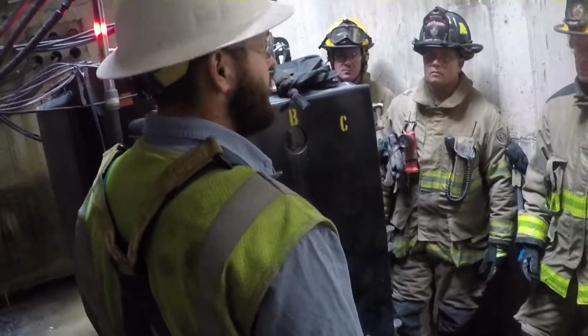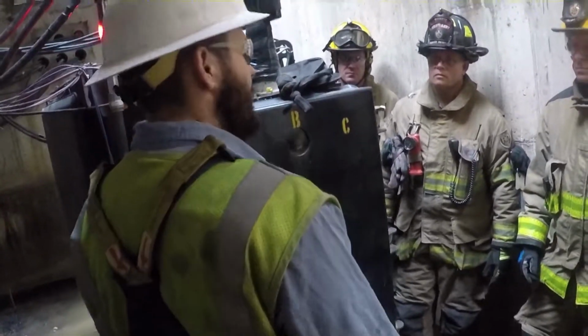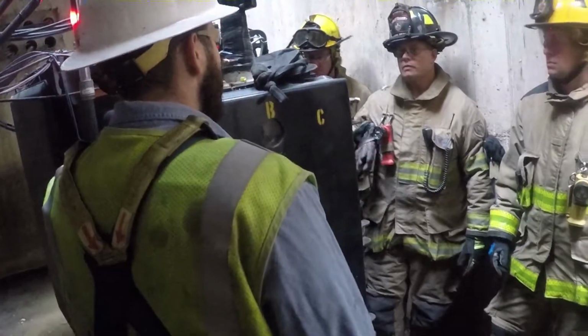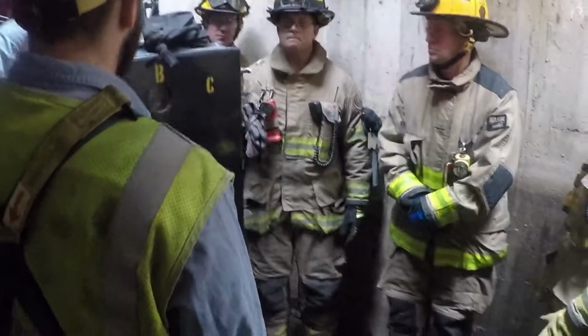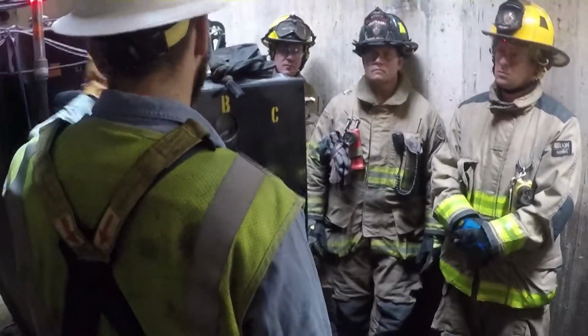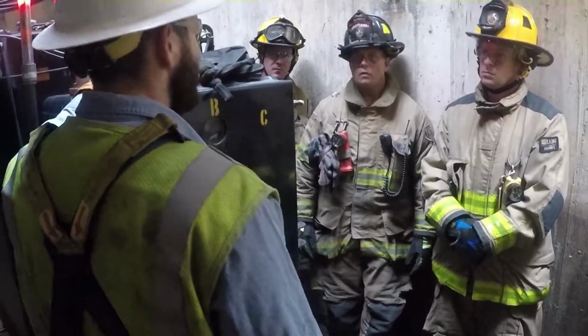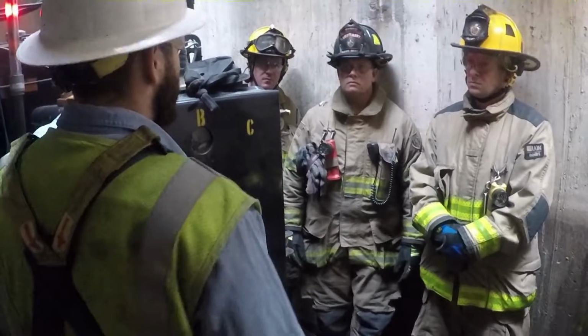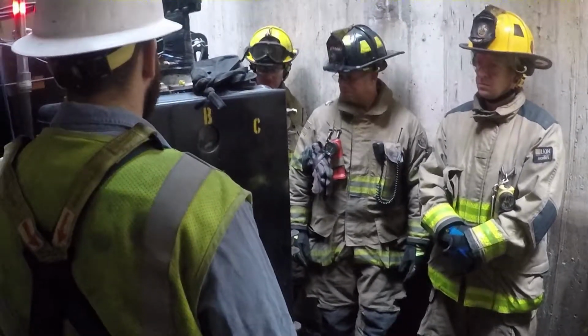We just want to do our thing, close it back in, and then they won't lose power. So the only way they would lose power is if they lost both of these. And these are both on 2 separate circuits coming from Heyman - this will be Heyman 1, Heyman 2. So if you were to lose a feeder, they would still not experience any power loss.